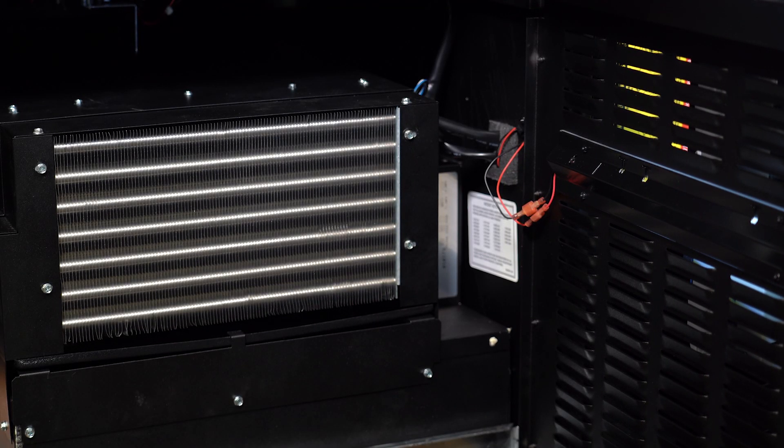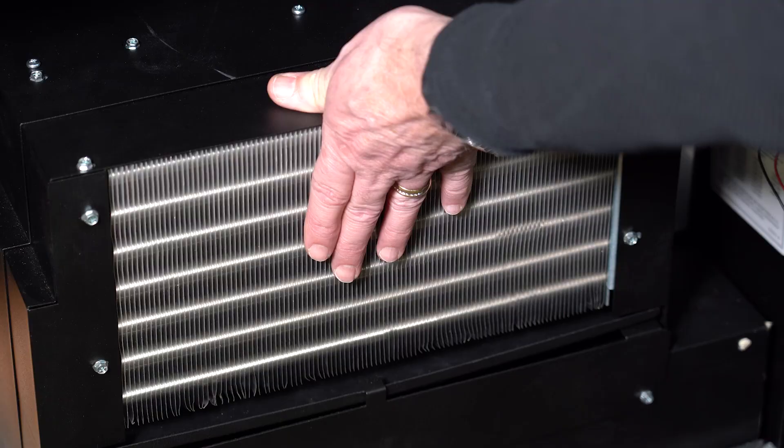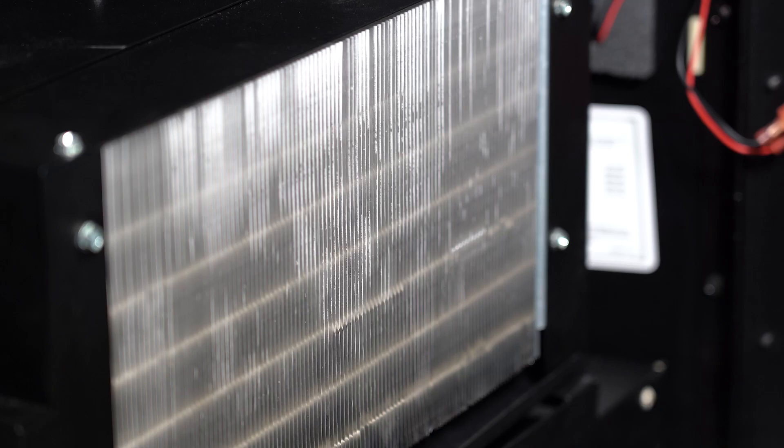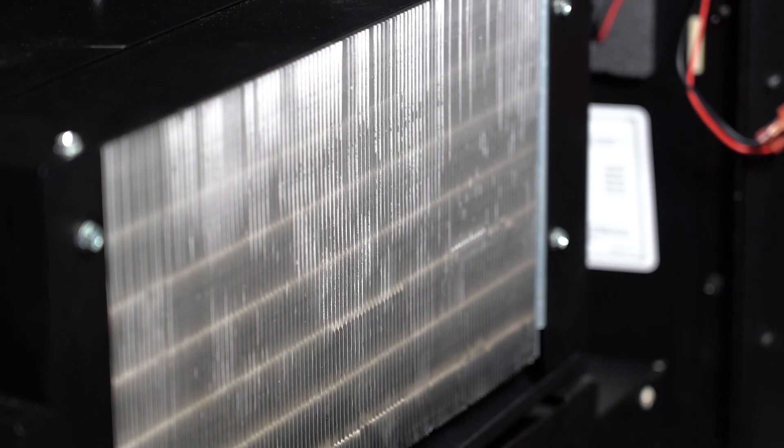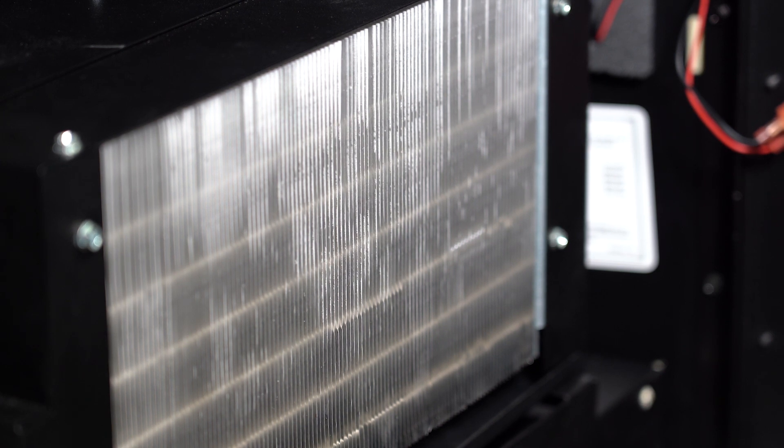If the machine is still not cooling, open the door and make sure the evaporator coil here is not iced over. The buildup here serves as insulation to the refrigeration unit that prohibits cooling. If there is frost buildup here, check to make sure the evaporator fan is working.